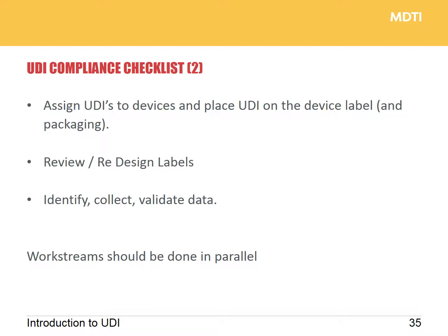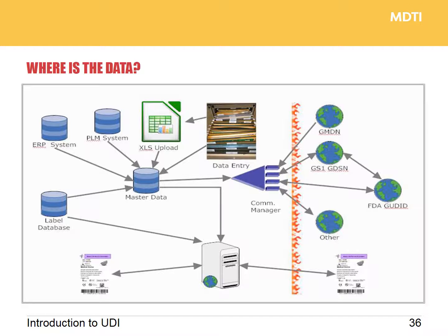Once you have your GS1 numbers, identify what is a base package, allocate a number to that base package, and then look to start placing that on device labeling — review and redesign labels for date formats, etc. The key and biggest job is to identify, collect, and validate the core data set. We would recommend that these work streams should, wherever possible, be done in parallel. In regards to the data you'll require for GUDID and UDI, where is that data going to be? Some will be in Excel spreadsheets, some on paper, some in ERP systems. Even if you have the data, it's not necessarily in the correct format for sending to the GUDID. Gathering this data together is the longest job you will have for UDI compliance.